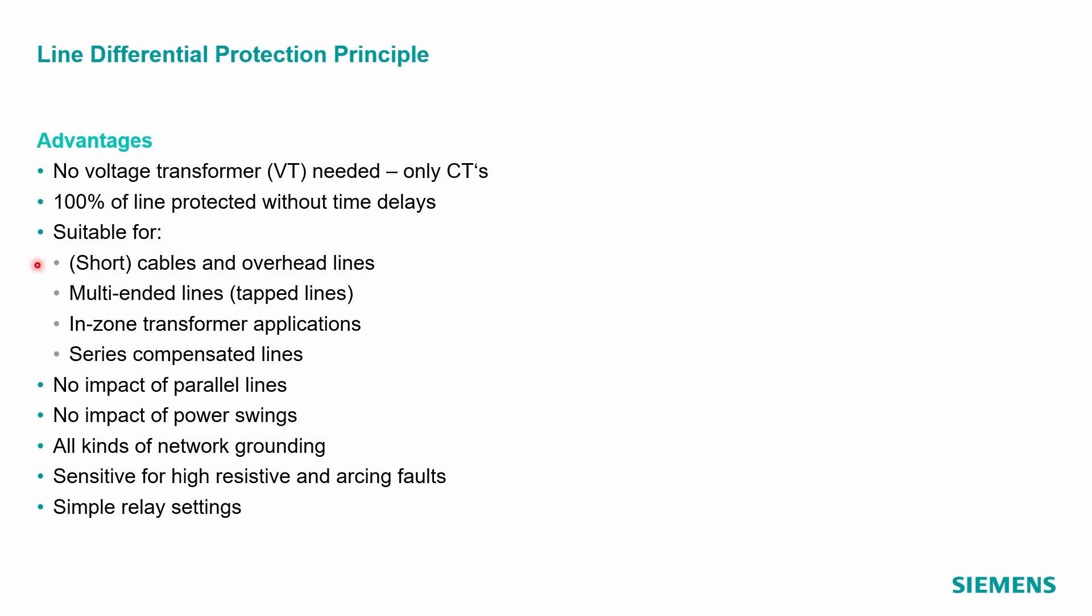Therefore, it's suitable for short cables or overhead lines. It's also possible to use it for multi-ended lines, so tapped lines, and also applications with a transformer in the protected zone, or for series compensated lines. There is no impact for parallel line switching states or power swings. All kind of network grounding can be considered. It's very sensitive for high resistive or arcing faults. And finally, the relay settings are quite simple.